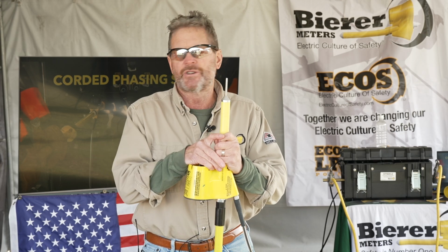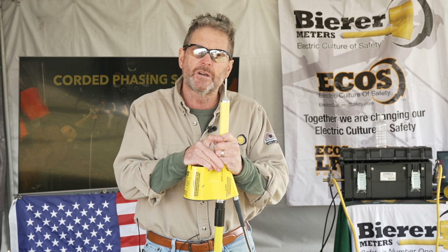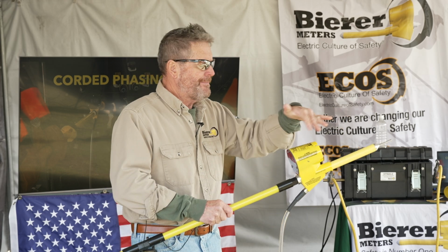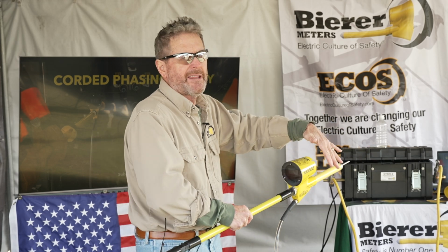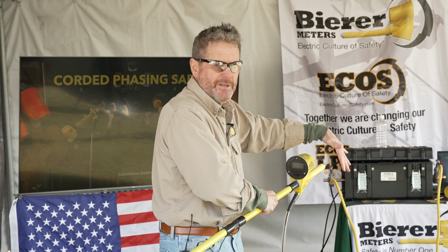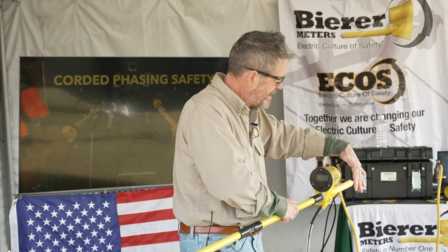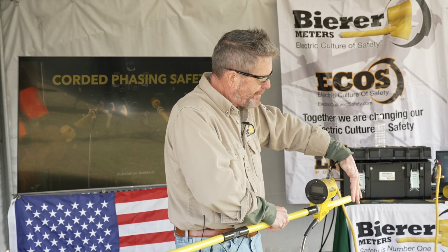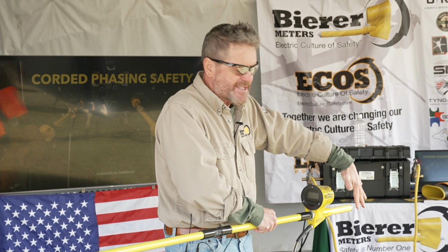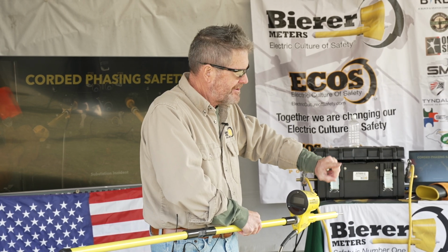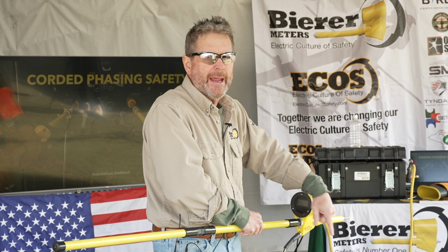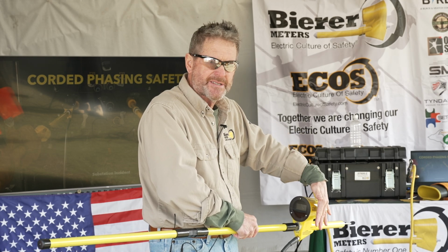Show us the picture. Sure enough, they showed us the picture, and the hot bus was over here on the right side of the meter. If you're looking at the meter head as the lineman using it, that's what happened. The picture showed the equipment, the hot bus, and you could see the explosion that happened - like a moon crater on the gray paint of that equipment, with the hot bus right there.